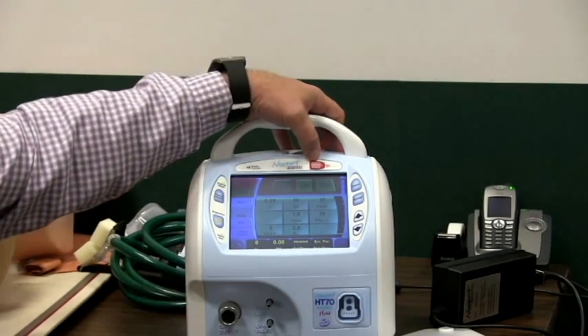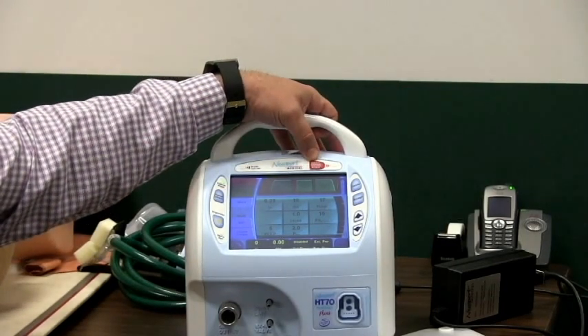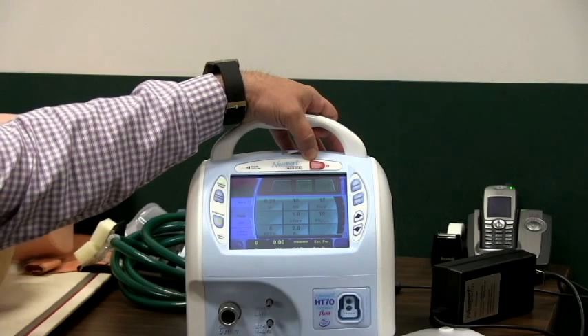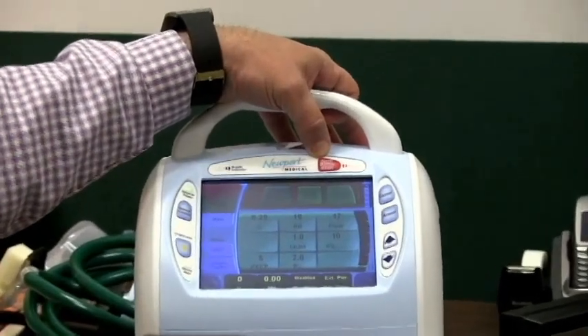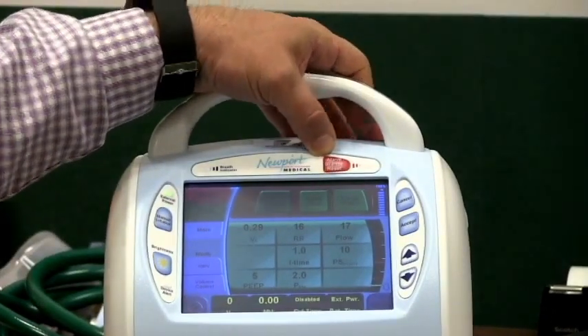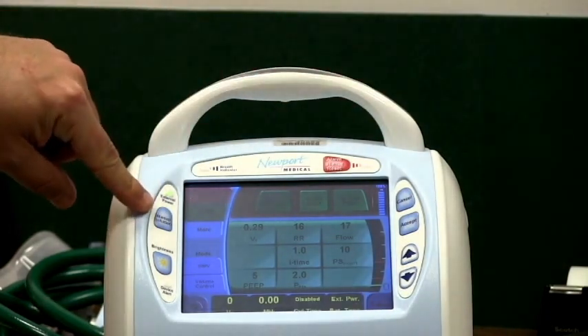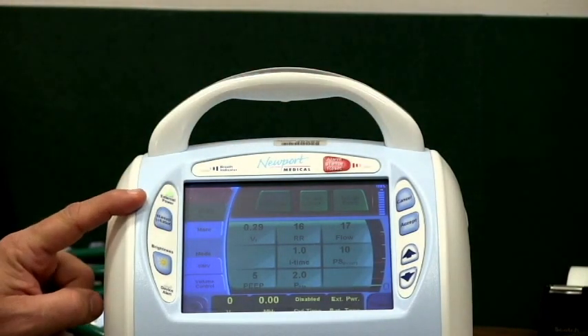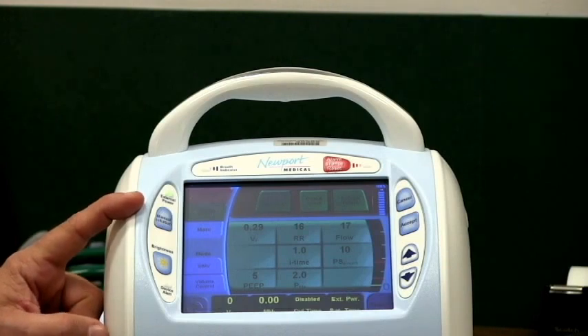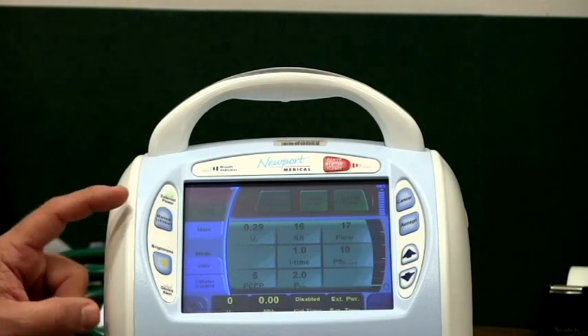Here on top of the unit you also have your alarm silence button. Let me zoom in just a little bit for you. Good. And then over here you have your manual inflation button. The manual inflation button is similar to, or exactly like, an inspiratory hold. The inspiratory hold is not something that we're going to routinely use to any degree, and probably most of you will not ever utilize it unless you're going to, for whatever reason, obtain plateau pressures and things like that.